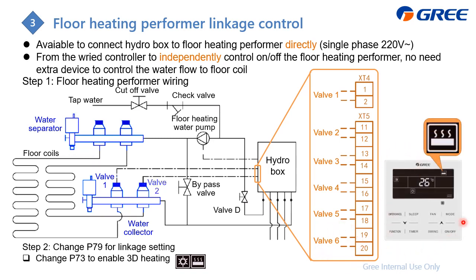On the wire controller, here is a floor heating mark. For example, this time we're going to control this valve 2 to conduct the hot water through this floor coil. We can just turn on this valve 2, and first of all do the wiring of this valve 2 to here, which is to this XT5, 11 and 12. Then this hot water can send into this valve 2 directly, and of course the command is from here. After you do the linkage with the wire controller, which is to do the linkage to the indoor unit, then you can achieve this 3D heating. That means the indoor unit doing heating, and also the floor coil is also doing heating. That means you can heat up the room from every direction.